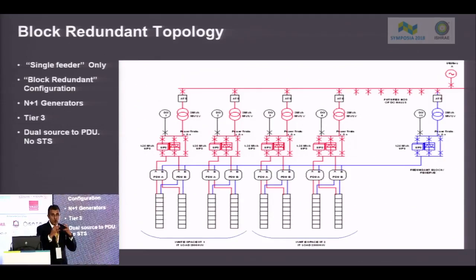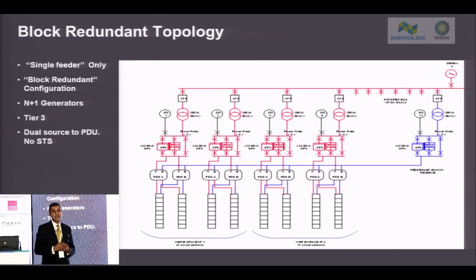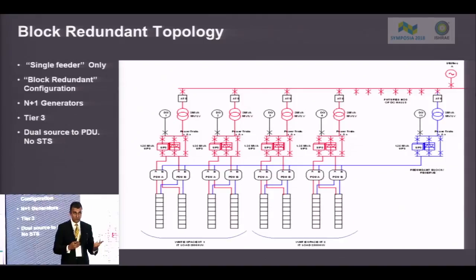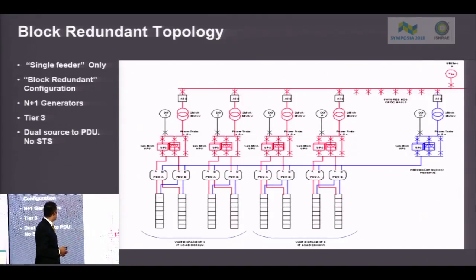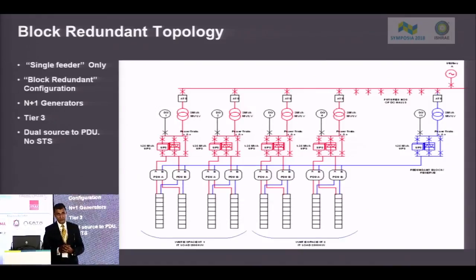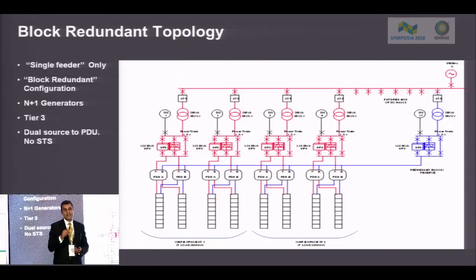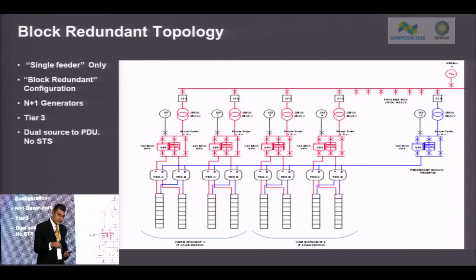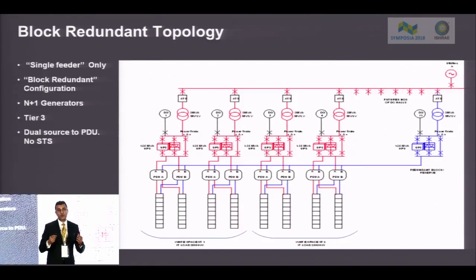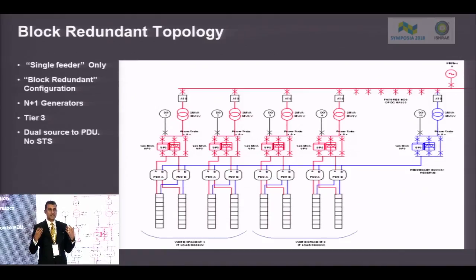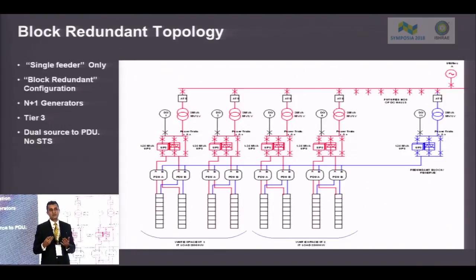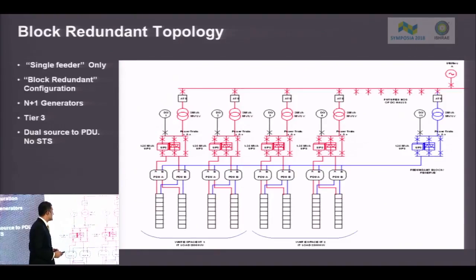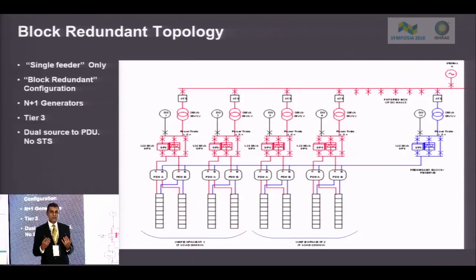With the core topologies for reliability, then comes the various strategies for controlling capex costs and improving efficiency in terms of the topology. What you see here is a block redundant topology. In this topology, instead of providing 200% UPS load for the IT, as I said earlier, in a tier 3 usually, or even a tier 4, it's a 2N topology, right? So you're providing 200% of UPS capacity for the IT load. Now we look at the various strategies in a block redundant topology. Now we can reduce capex because we're providing 130, 140% in general UPS capacity for the IT load.